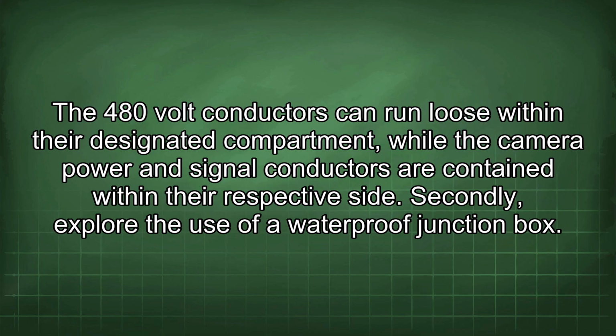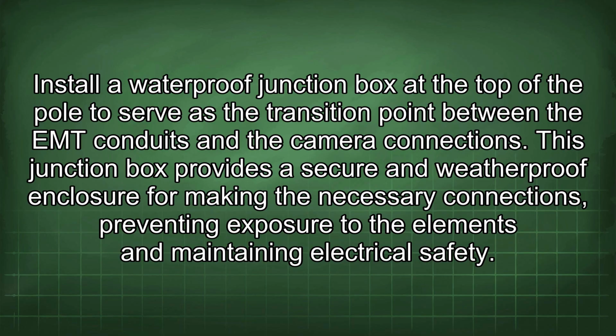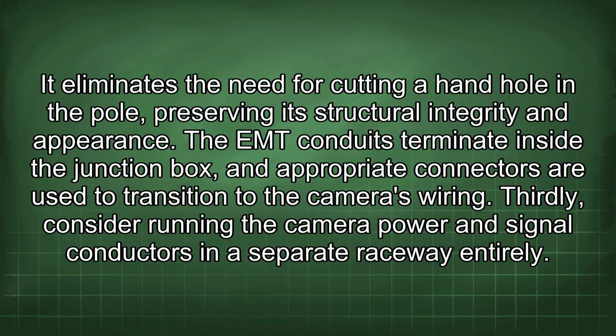480-volt conductors can run loose within their designated compartment, while the camera power and signal conductors are contained within their respective side. Secondly, explore the use of a waterproof junction box. Install a waterproof junction box at the top of the pole to serve as the transition point between the EMT conduits and the camera connections. This junction box provides a secure and weatherproof enclosure for making the necessary connections, preventing exposure to the elements and maintaining electrical safety. It eliminates the need for cutting a handhole in the pole, preserving its structural integrity and appearance. The EMT conduits terminate inside the junction box, and appropriate connectors are used to transition to the camera's wiring.